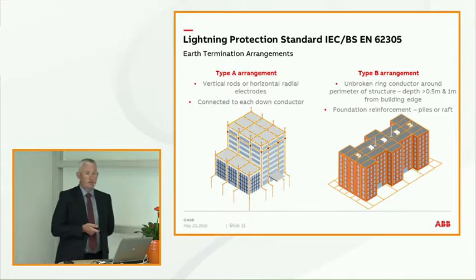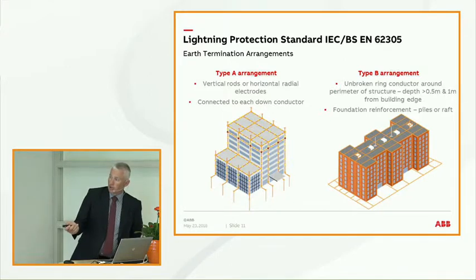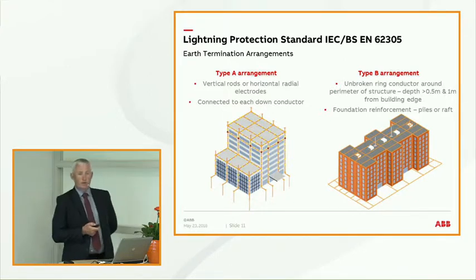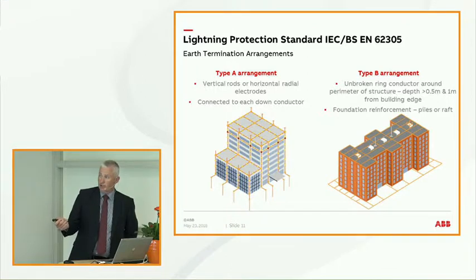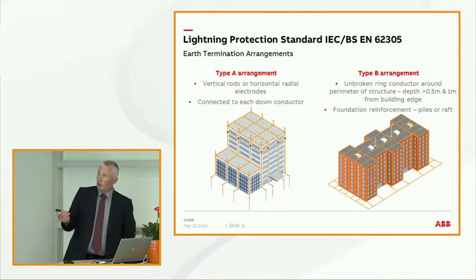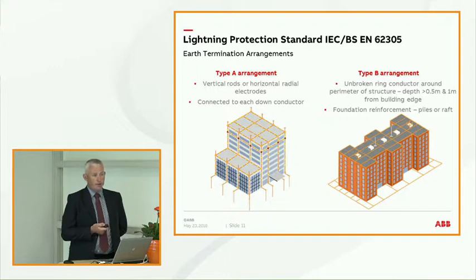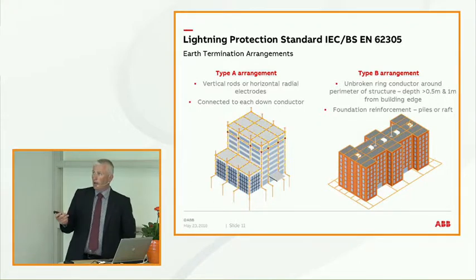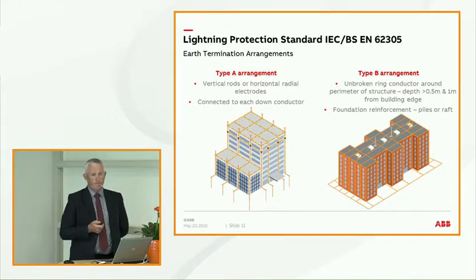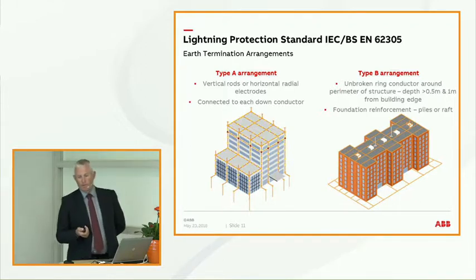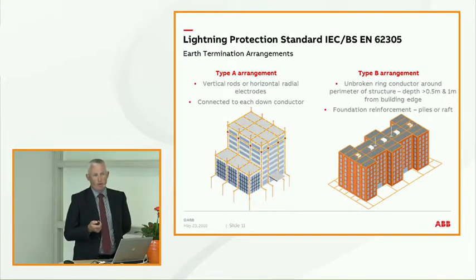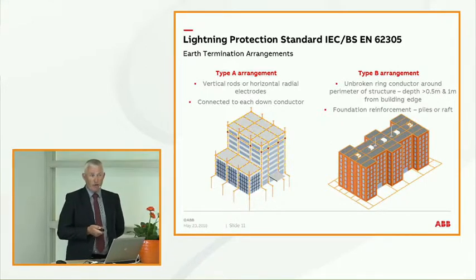With lightning protection, there are two general earthing arrangements. As you can see, you've got the Type A arrangement, which is the most common. So you've got the Faraday cage system, and that will take the lightning strike to earth at several points. You've also got the Type B arrangement. The standards introduced on the 1st of September 2006, now the IEC standards, try and push a Type B arrangement. This will allow the use of reinforcement bars in the structure. Maybe an air termination network might be connected to a ring earth conductor at the bottom. So we can use the foundations as part of that earthing system.